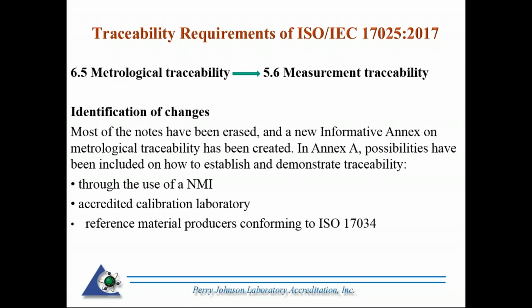However, the 2017 standard has two annexes, A and B. Annex A contains more informational material in regards to traceability, so we're going to go over some of the information within Annex A. The 2017 standard is specific: you can get traceable measurements through the use of an NMI, your National Metrology Institute, or accredited calibration labs. So we'll look at that. And we'll also touch on reference material producers, conforming to ISO 17034.